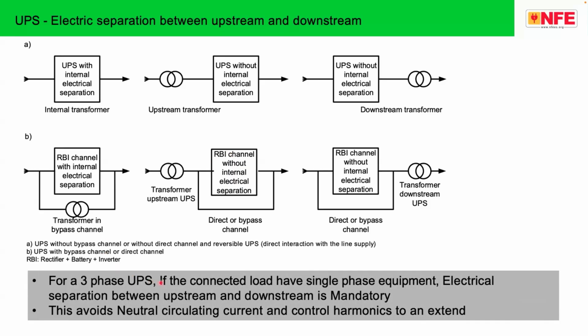For a three-phase UPS, if the connected load has single-phase equipment, electrical separation between upstream and downstream is mandatory. You must use an isolation transformer. This avoids neutral circulating current and controls harmonics to a great extent. Please take care of this.